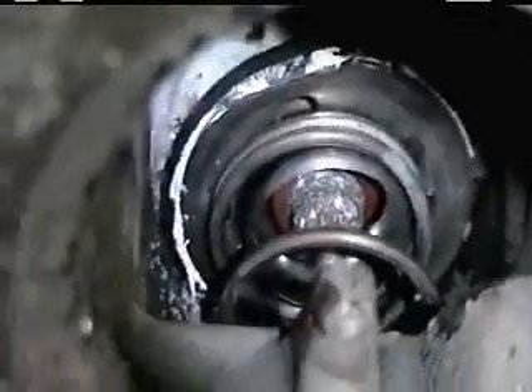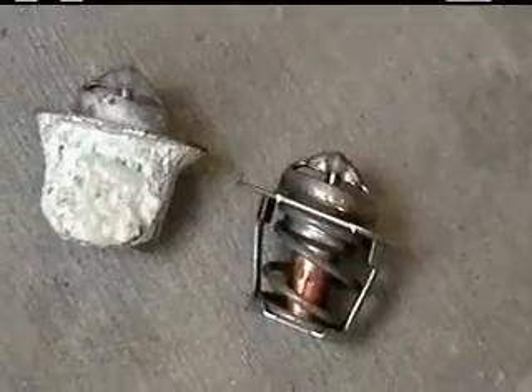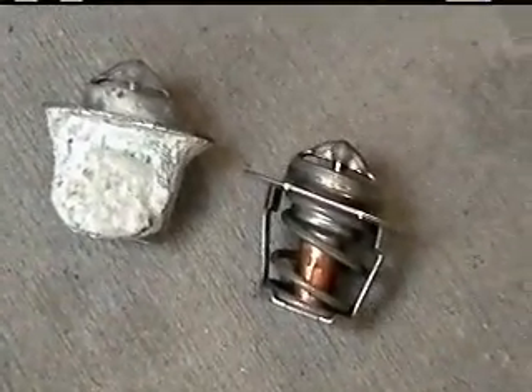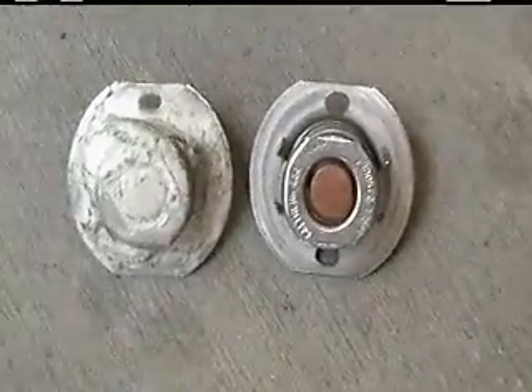Okay, this particular view here is of the unitherm governor, and we're going to expand on this a bit more in a second here. But you're looking inside of the header. We're examining the bypass valve and unitherm governor. What you're seeing there is evidence of a lot of scaling and calcification inside of the header. This is blocking the water flow and preventing the heater from operating properly. More evidence of the scaling and calcification.